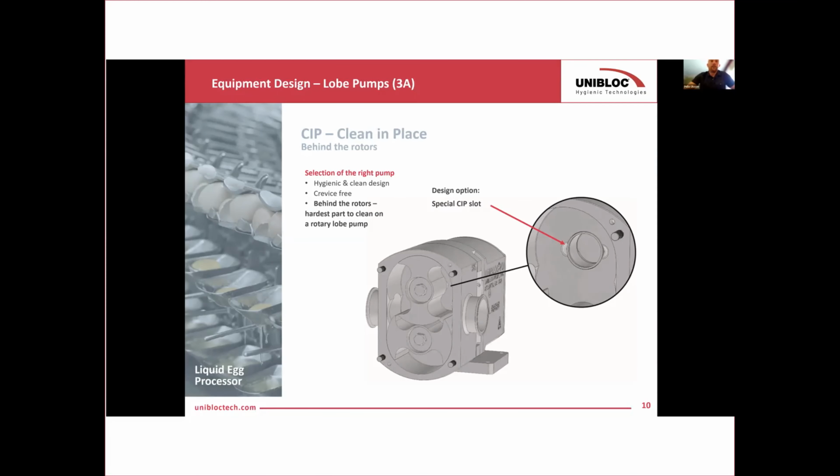He validated it. The pump is clean. It looks pristine. And the way they operate today, they still open up the cover, but they only have to visually look inside the pump and look for other damage. They no longer have to remove the rotors. So that's a big step forward for them.